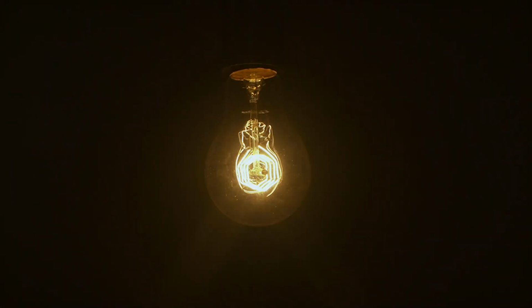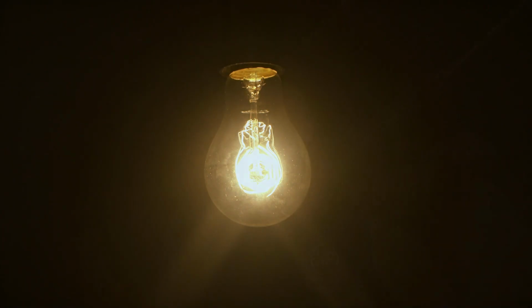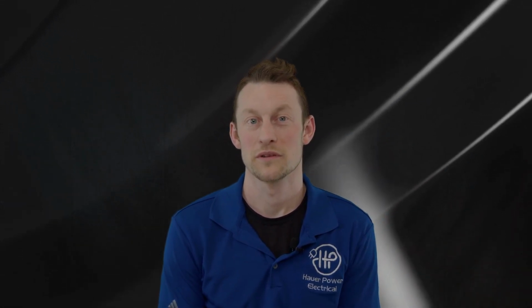But if you're having lights flickering, meaning that they go on and off, that's a connection problem, meaning there's going to be a break in the connection, or a connection isn't tight either at your switch or your light or somewhere in the feed, could be even at the breaker panel. As far as the dimming lights or the flickering lights, there's solutions for both, but oftentimes with dimming lights, it could be caused by poor grounding if it's excessive dimming, or it could be caused by bad light bulbs. Maybe they're really cheap bulbs and internally the LEDs just aren't up to snuff. As far as flickering lights, that's going to require an electrician's touch for sure, because somewhere there's a connection that needs a troubleshoot and repair.